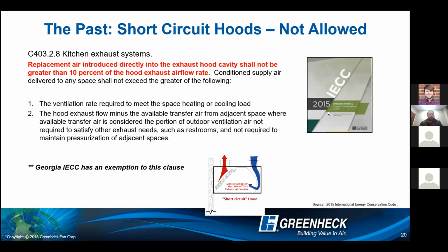So IECC 2015 essentially outlawed short circuit hoods. However, again, Georgia IECC has an exemption to this clause, but the way that was done is in red here: the replacement air introduced directly into the exhaust hood cavity shall not be greater than 10% of the hood exhaust airflow, which essentially eliminated short circuit hoods because those rely on 80 to 90%. Again, fully understanding that you guys have an exemption to this clause.